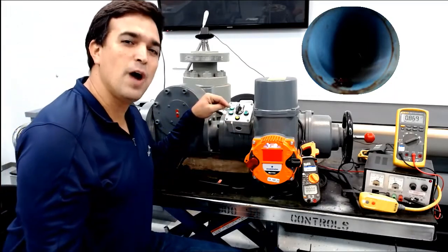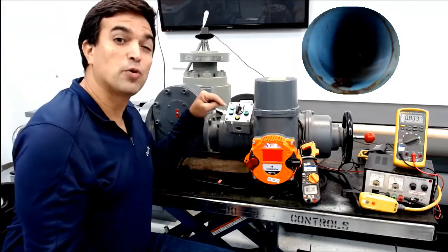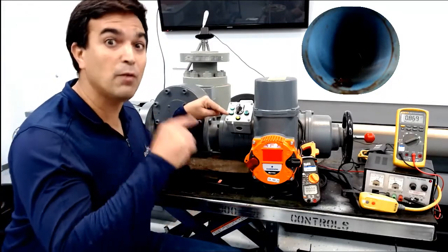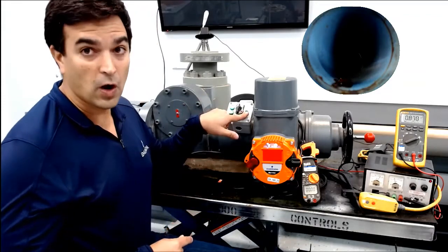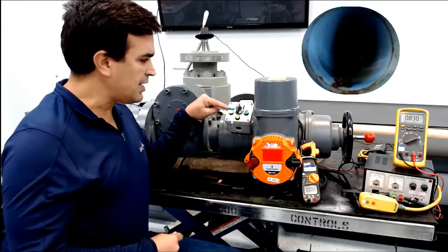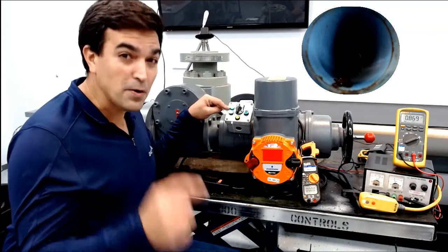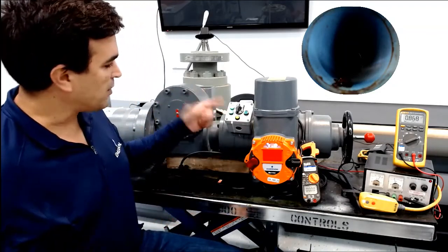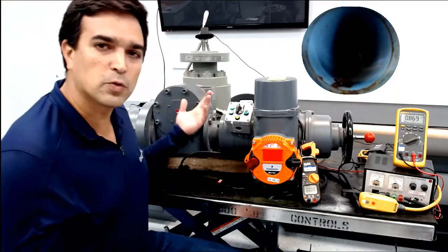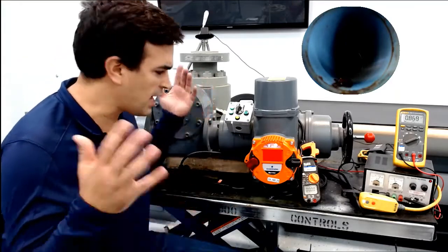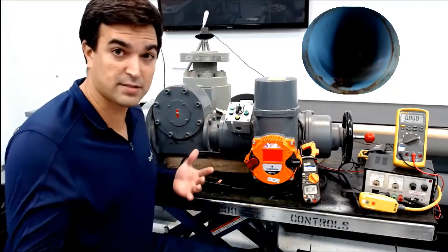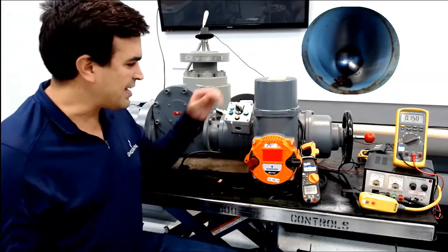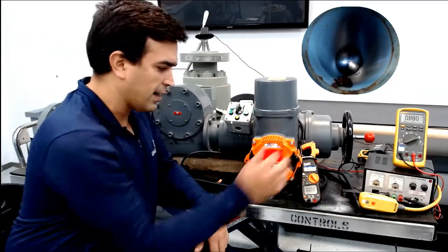But the cool thing here is that now, because you lost the main power supply, I don't know if you realize that, but you have the feedback here. So your DCS is going to have the feedback. Right now it's telling you, hey, the valve remains open. It's never closed. And it's also telling you with this light that the partial stroke that I did before was okay. So right now the valve is open. You want to trigger because your safety system, or your SIS system, wants to trigger, so you trigger. And that's it. In less than 5 seconds you close that valve.